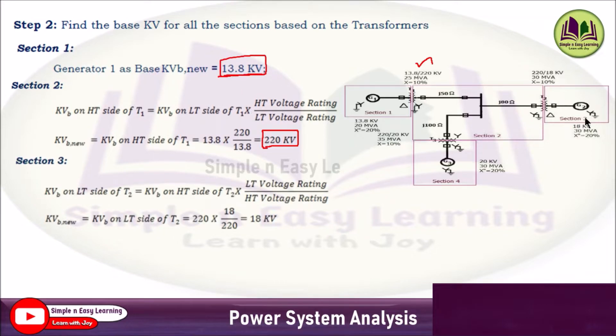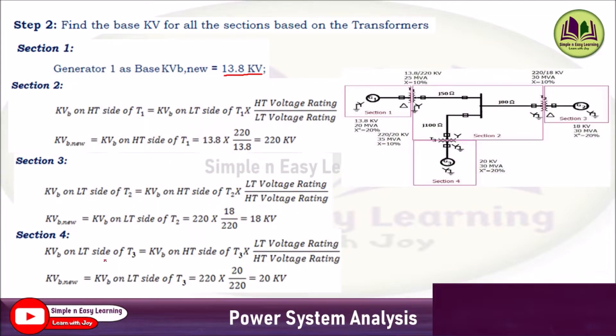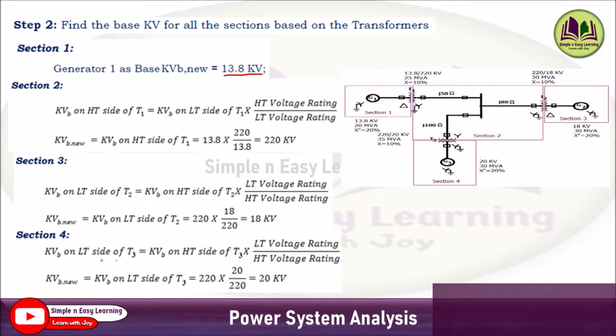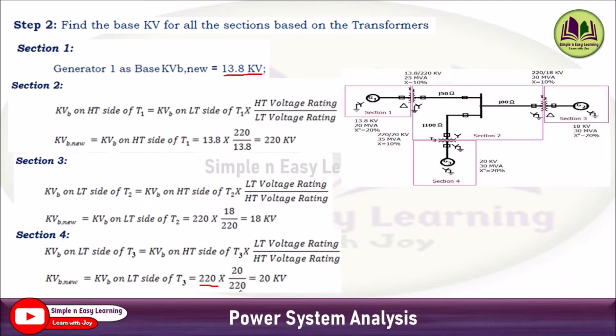For section 3 (LT side of T2): base kV = HT side base × (LT/HT rating) = 220 × (18/220) = 18 kV. For section 4 (LT side of T3): KVB = KVB on HT side of T3 × (LT/HT voltage rating) = 220 × (20/220) = 20 kV. These are the base kV values for all four sections.